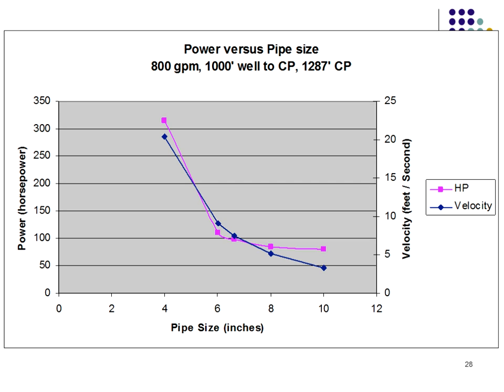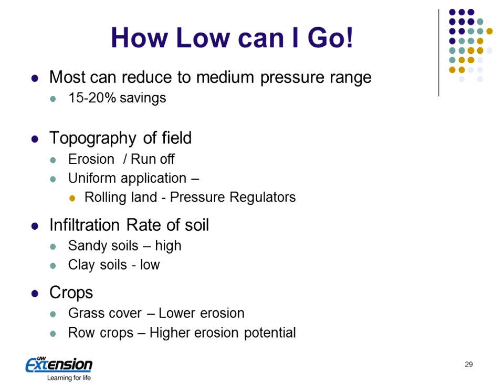Pipe size, I talked about how we can increase the velocity in the pipe. So this looks at horsepower versus pipe size. On a horsepower basis, which is the pink line, once we get above about 7.5 feet per second, this escalates rapidly. Our horsepower requirement increases quite rapidly. So we'd like to keep that below 7.5, or usually they design it at about 5 feet per second when you design a piping system, to keep the velocity head at a reasonable amount.